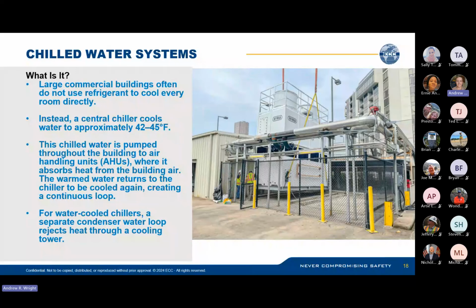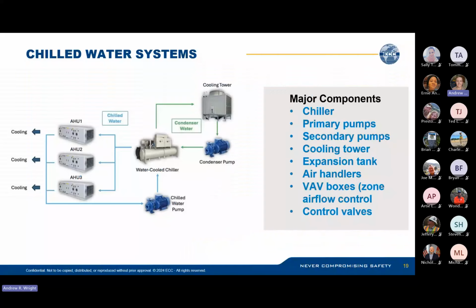Components of a chiller: you have your cooling tower, your pumps, expansion tanks, air handlers, VAV boxes, which are your zone airflow controls. It basically directs water from the chiller into certain areas, so that if one room's too cold or one room's too hot, you could adjust it essentially. And control valves.